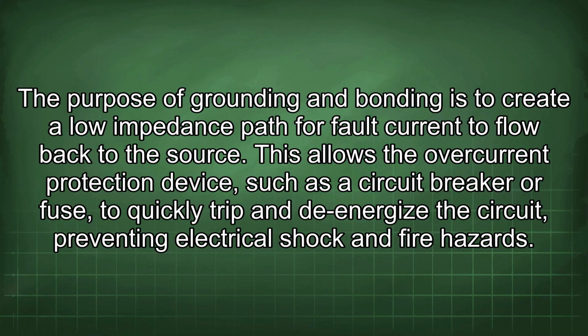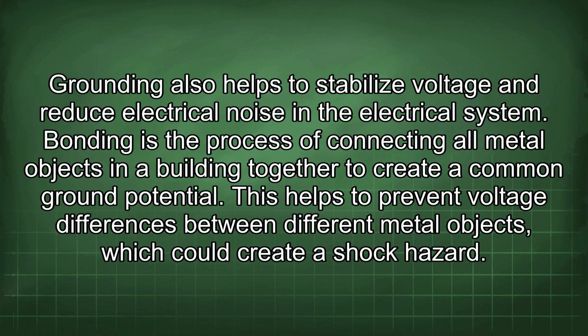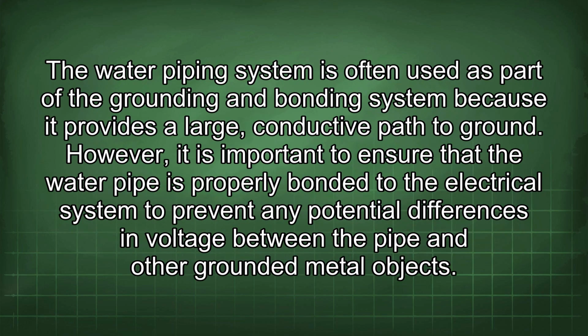This allows the overcurrent protection device, such as a circuit breaker or fuse, to quickly trip and de-energize the circuit, preventing electrical shock and fire hazards. Grounding also helps to stabilize voltage and reduce electrical noise in the electrical system. Bonding is the process of connecting all metal objects in a building together to create a common ground potential. This helps to prevent voltage differences between different metal objects, which could create a shock hazard. The water piping system is often used as part of the grounding and bonding system because it provides a large, conductive path to ground. However, it is important to ensure that the water pipe is properly bonded to the electrical system to prevent any potential differences in voltage between the pipe and other grounded metal objects.